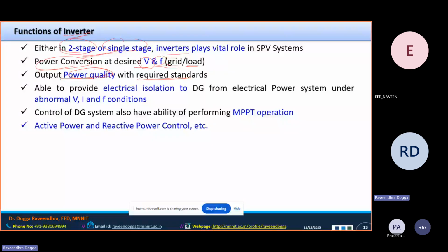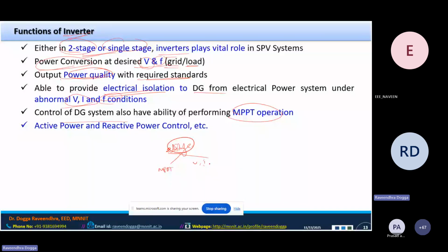It should also have proper electrical isolation to the DG from the electrical power under abnormal voltage, current, or frequency conditions. The control of DG should have the ability to perform all functions. If you have two stages, there is no problem, but with only one stage power conditioning unit, it should be able to take care of MPPT, voltage control, current control, active power, reactive power, and frequency control. A lot of features need to be incorporated.